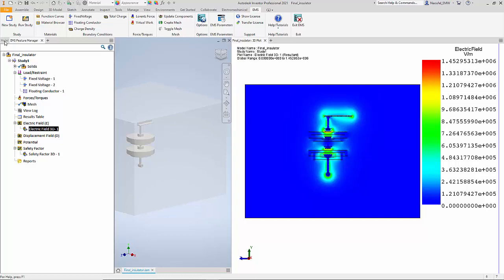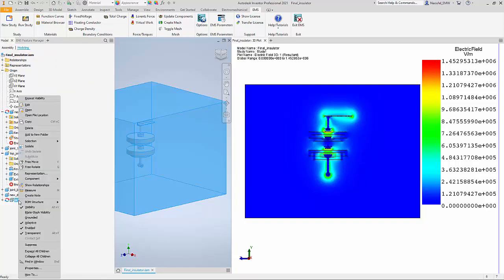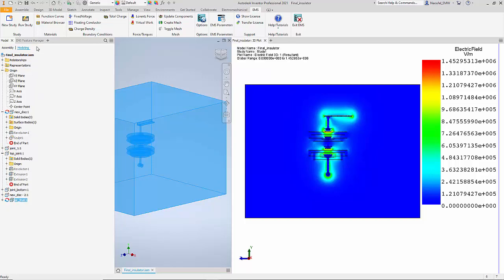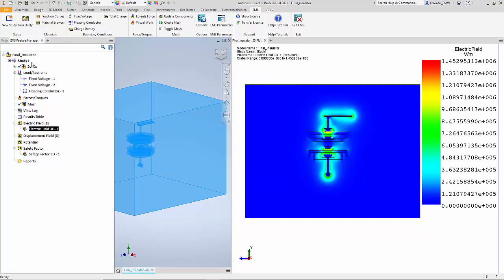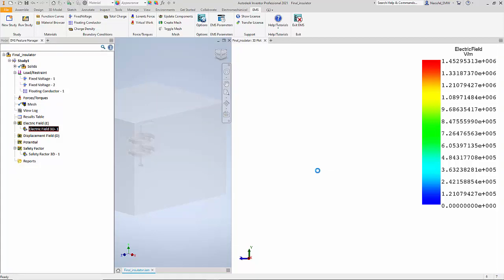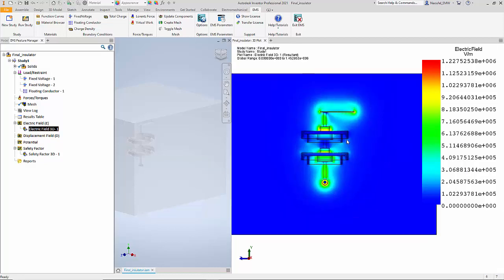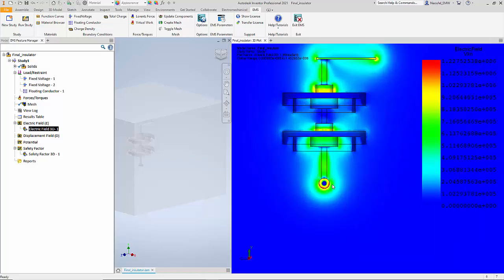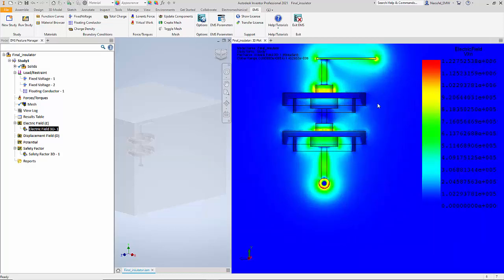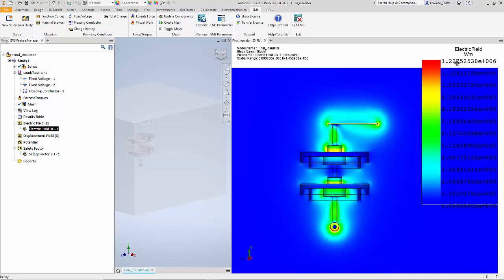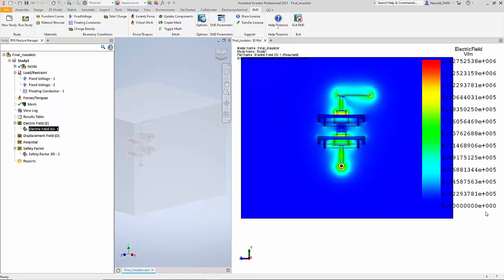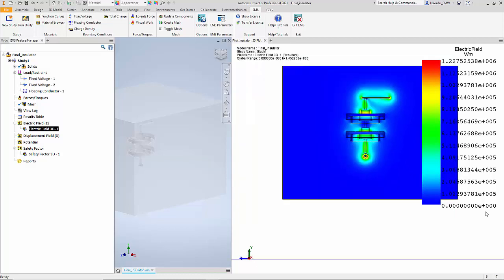Now another thing we can do is isolate the air and look at only the air. I go back to EMS and double click on the electric field plot. This will hide all the solid components and we are able to only look at the electric field distribution in the air region. You can see that the maximum electric field is right in the bottom and in these corner areas, and that value is around 1.2 million volts per meter. We know that the air breaks down at 3 million volts per meter, and as a result we can be sure that the breakdown of the air has not occurred for this operating voltage.